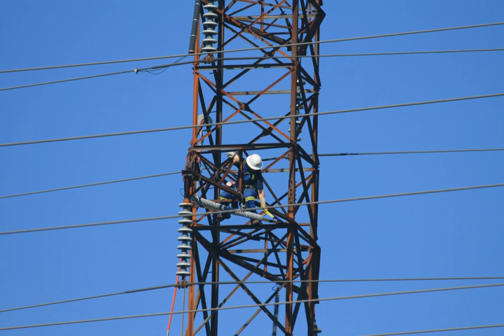Lightning arrestors are used to protect electric fences. They consist of a spark gap and sometimes a series inductor. Lightning arrestors can form part of large electrical transformers and can fragment during transformer ruptures. High-voltage transformer fire barriers are required to defeat ballistics from small arms as well as projectiles from transformer bushings and lightning arrestors, per NFPA 850.